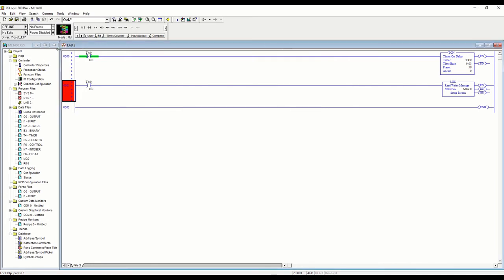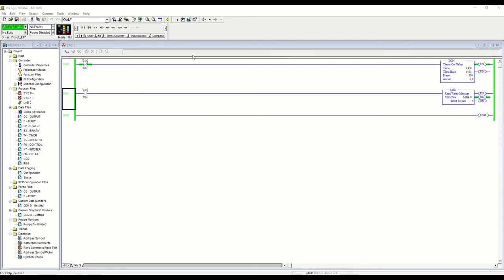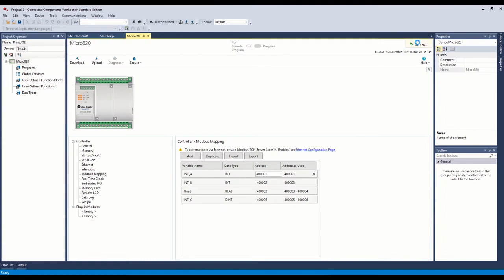We'll save that. The next step is to download this to the controller, so let's go ahead and do that. There we go — we're running, we're online with the controller. You can see the timer running. This is going out and reading that register every half second, and you can see we're getting a done bit with no errors. If we open up our N7 register here, we have a zero, so let's go over to our Modbus slave device and connect to it.